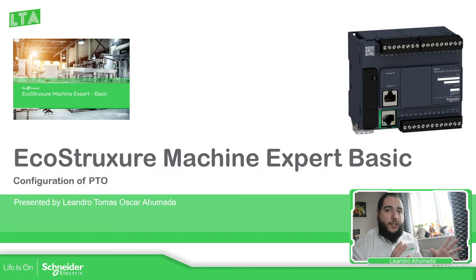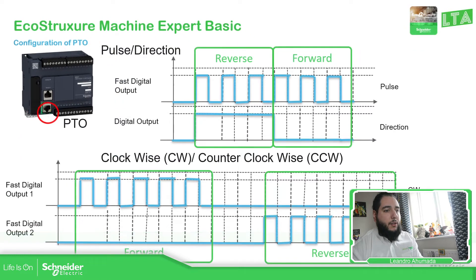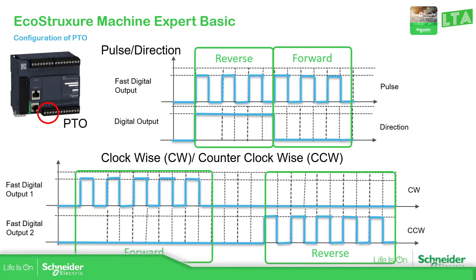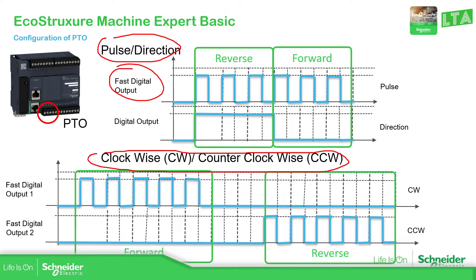In the previous video we saw the explanation about the PTO and PWM. Now we're going to focus on the configuration of the PTO. Looking at this graph, we can see the different ways to configure the output of the PTO on the M221. If we use pulse direction, we need one fast output. If we use clockwise/counterclockwise, we need two. So if you use pulse direction, you have the possibility to use another axis; otherwise you consume both axes in one.